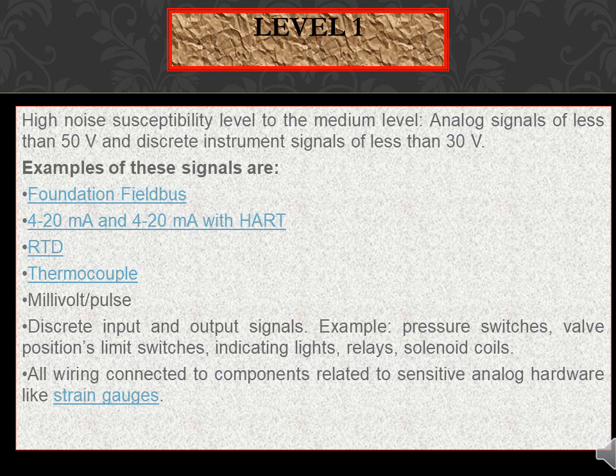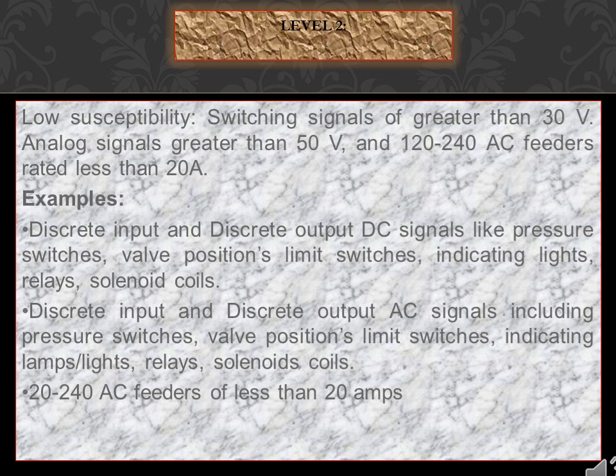Examples of Level 0/1 signals include Foundation Fieldbus, 4 to 20 milliampere, 4 to 20 mA with HART, RTD, thermocouple, millivolt, pulse, and discrete input/output signals such as pressure switches, valve positions, limit switches, indicating lights, relays, and solenoid coils. All wiring connected to sensitive analog hardware like strain gauges also falls under this level. Level 2 covers low susceptibility switching signals greater than 30V and analog signals greater than 50V.